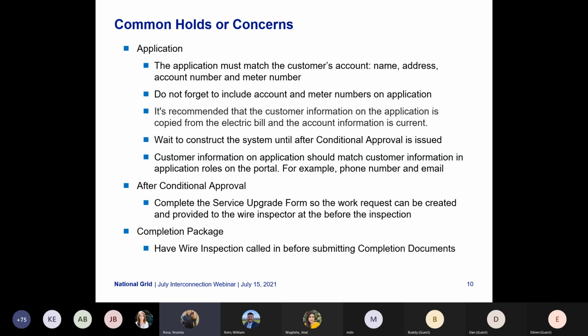We tend to see that a number of cases will go into completion documents and that service upgrade form isn't filled out yet. It just makes it a longer process for you to get that meter set because your work order hasn't been cleared by the inspector, but your completion documents are in. So if you do that right after you get the conditional approval, then you'll have that work order number ready and available for that inspector when he comes out to inspect your system.